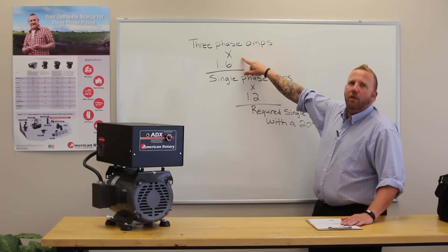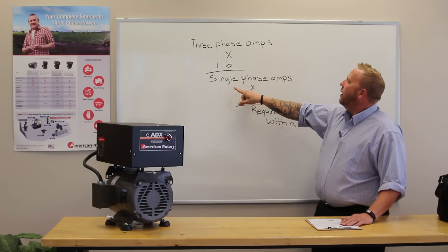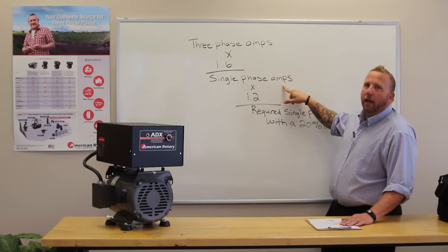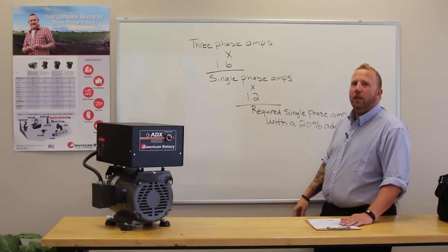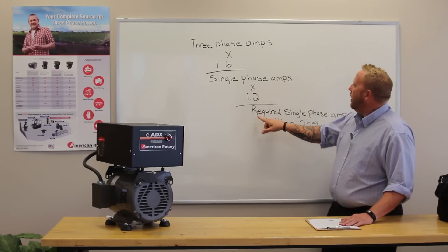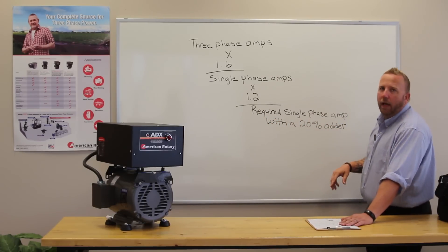If you take your three phase amps of your load, multiply that by 1.6, you're going to get your single phase amps. You multiply that by 1.2, that's 20% above what your load is, and you're going to get your required single phase amps with a 20% adder.